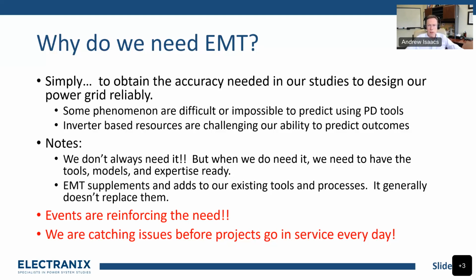We're also seeing events in the power system that are reinforcing that need. We see large chunks of generation tripping off that is impossible to predict. We see subsynchronous control interaction events which show that we're not able to study this without EMT studies. And the other thing I'll note is that in the course of the work we do, every day we're doing these EMT studies, we catch these issues -- we catch ride-through issues, interaction issues, oscillation issues, instabilities, etc., before they go into service. And this has, for me anyway, and for us living this EMT life every day, validated the need to do it.